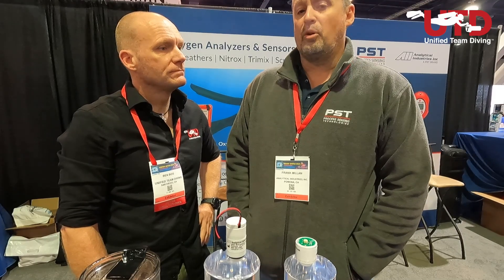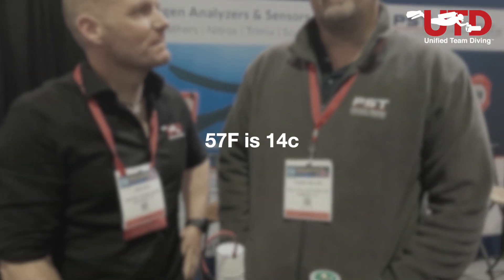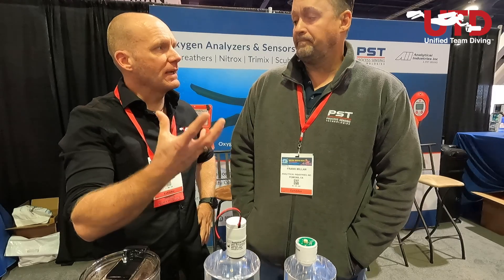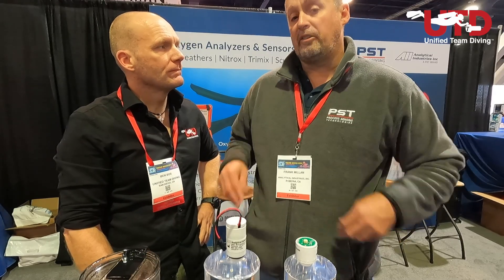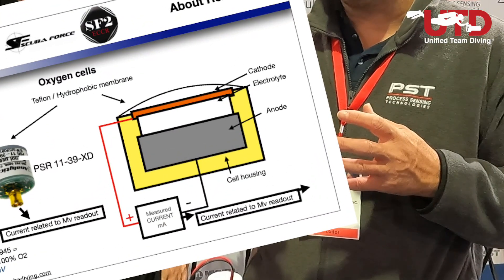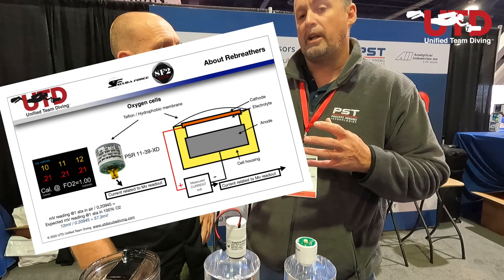And then make sure that temperature storage-wise is a nice cool 57 degrees F. Temperature is the biggest deterrent to the life of the sensors, with the exception of O2 concentration. High temperature can evaporate the electrolyte inside; it'll also expand the sensing membrane to allow more oxygen through and start the oxidation process, which consumes the lead anode inside the sensor much more quickly.